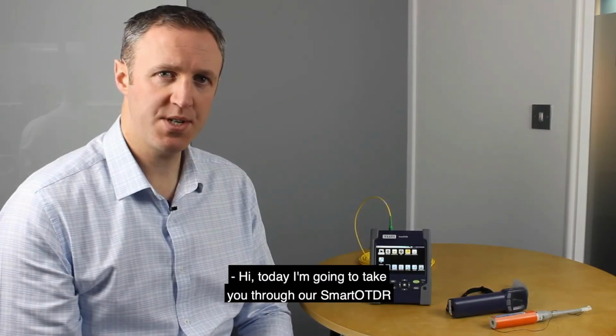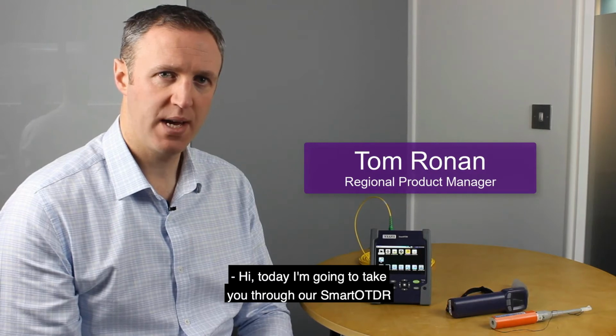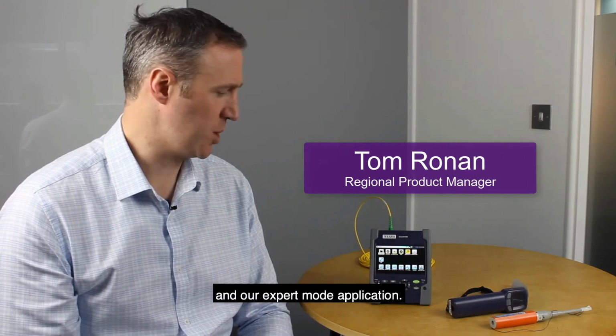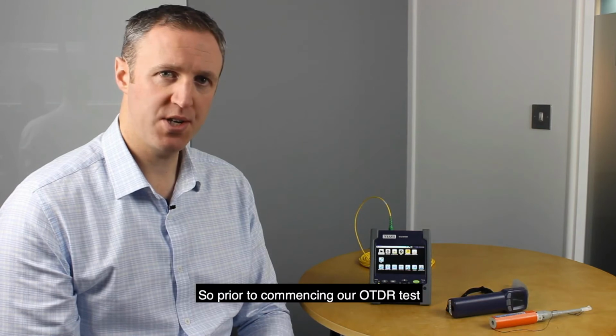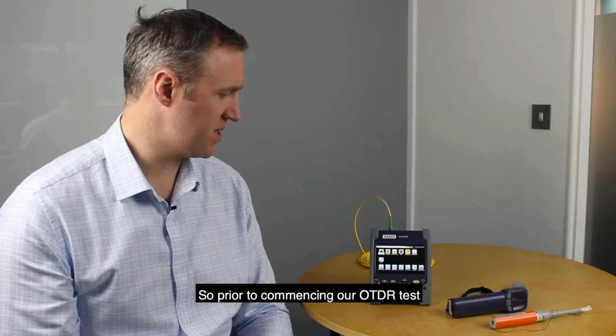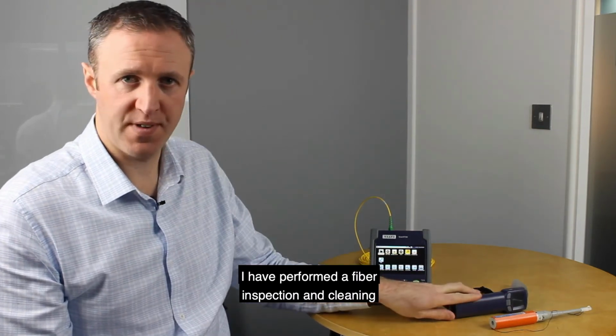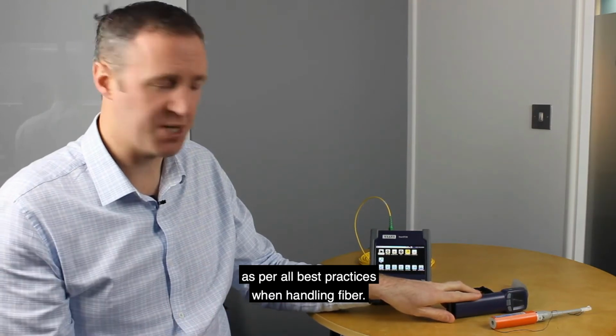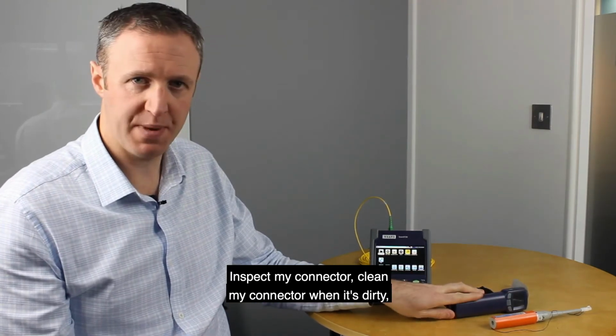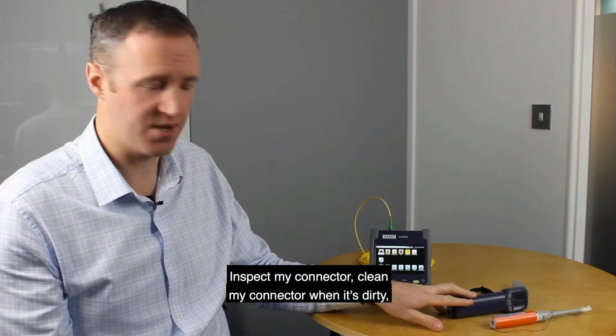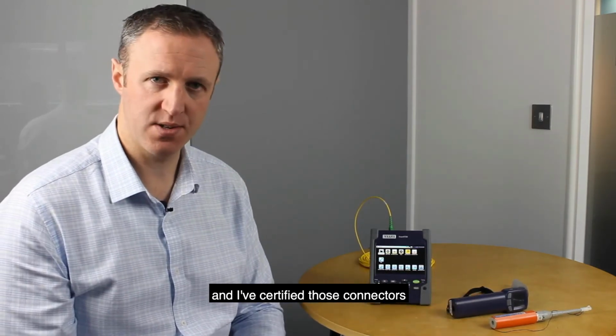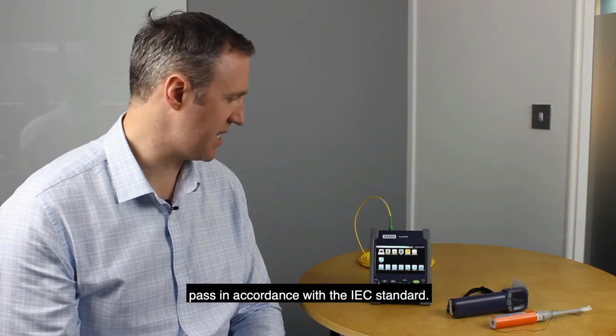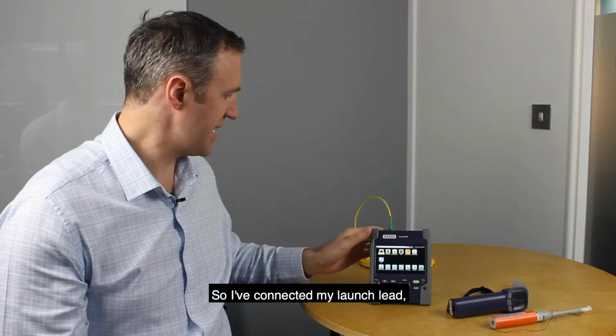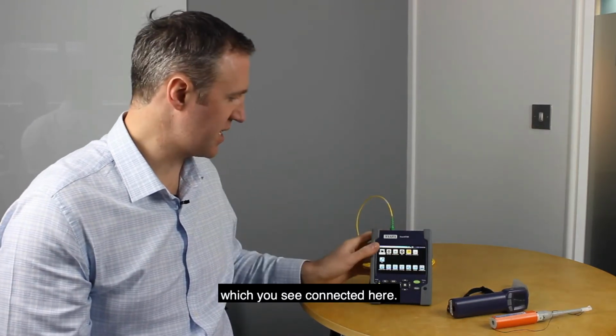Hi, today I'm going to take you through our SmartOTDR and our expert mode application. So prior to commencing our OTDR test, I have performed a fibre inspection and cleaning as per all best practices when handling fibre: inspect my connector, clean my connector when it's dirty, and I've certified those connectors pass in accordance with the IEC standard. So I've connected my launch lead, which you see connected here.